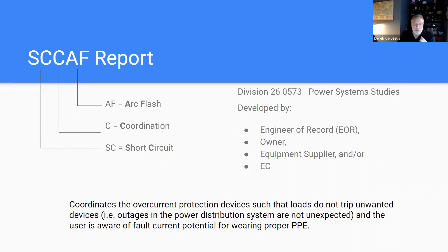And the reason I bring that up, why that's very important, is because everything is modeled in the short circuit study as well as the coordination table based on the manufacturer providing that right piece of equipment. So if that equipment is wrong at the factory, or if it's wrong at the integrator, that whole study needs to be remodeled and redone. So you as a commissioning agent, if you're doing factory witness testing of switchgear or of a generator, you should have a draft or at least a preliminary review of the SCCAF report with you so you can validate that manufacturer, model, serial number.